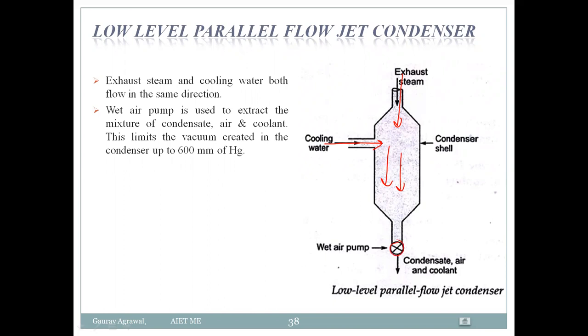From the low level parallel flow jet condenser, we extract three outputs: an air pump removes air, condensate is removed, and the coolant is also taken out. The vacuum pressure maintained here is approximately 600 mm of Hg.